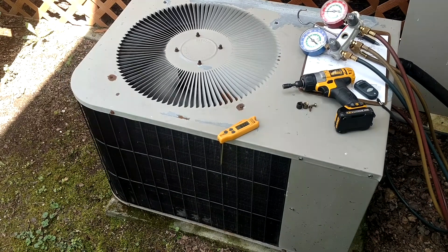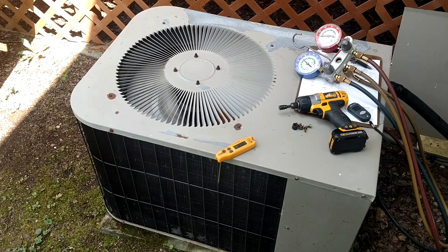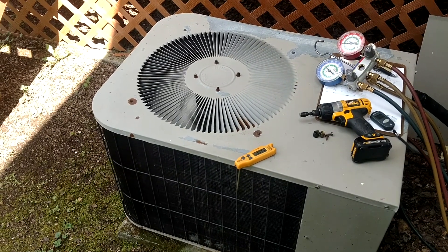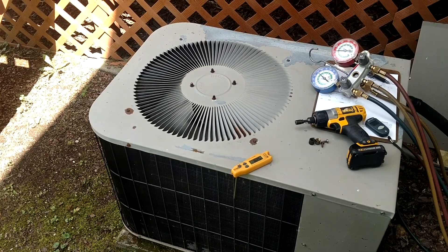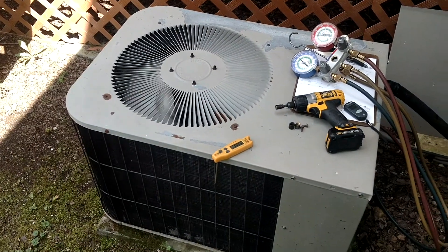It's running great. I remember back then I had a bad defrost board — I changed the defrost board out on it. Found a little bit of a refrigerant leak in the service valve areas, sealed them up, put the caps back on with some Nylog under them. And it hasn't leaked any since. Put a little gas in it back then and 16 years later she's still going.